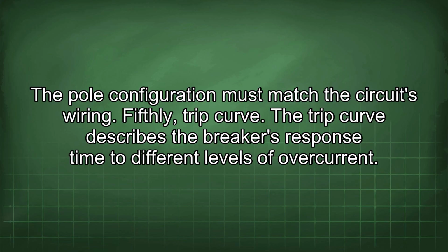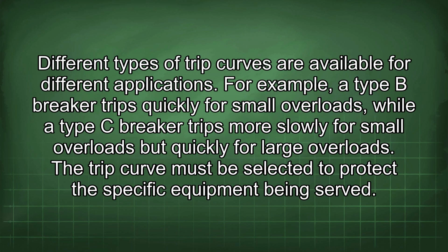Fifthly, trip curve. The trip curve describes the breaker's response time to different levels of overcurrent. Different types of trip curves are available for different applications. For example, a Type B breaker trips quickly for small overloads, while a Type C breaker trips more slowly for small overloads but quickly for large overloads. The trip curve must be selected to protect the specific equipment being served.